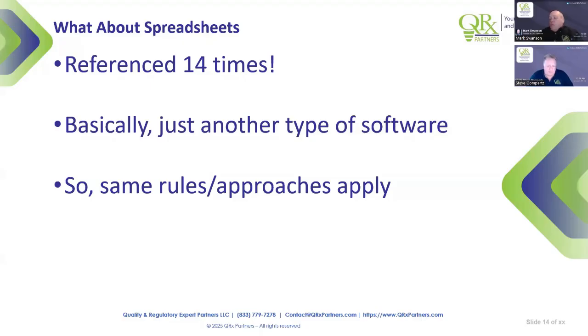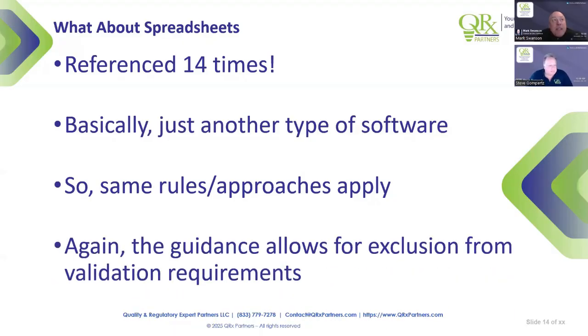Yeah, I think it's a good point. If your formula is a basic addition, add these three cells together, that's really simple to validate. But if instead behind that is some macro that's got 40 lines of code, that's a little different, a different type of testing. Pivot tables would be another one. It's a little more complex version of applying the basic functions. And again, that's why you need to evaluate the risks, and the risk profile of the software and its functionality. But again, validation simply means that you get the result that you expected.